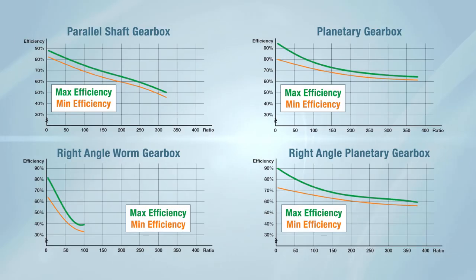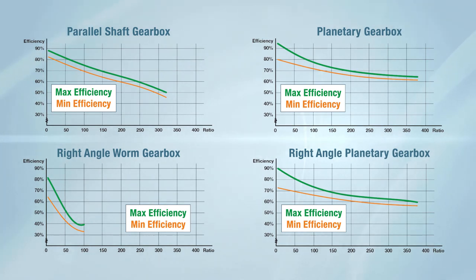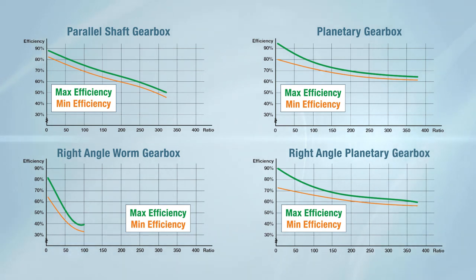Next, we have the same efficiency curves for the four most common reducer types. As we already said, simply multiply the motor efficiency by the reducer efficiency to obtain the total efficiency for a gear motor. There's quite a bit more we could say about reducers and gear motors, but that's for an entirely different series.